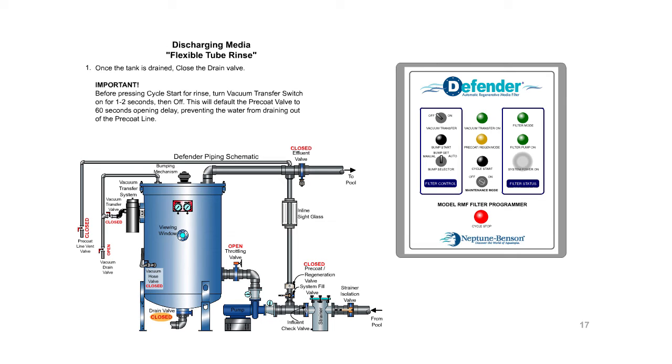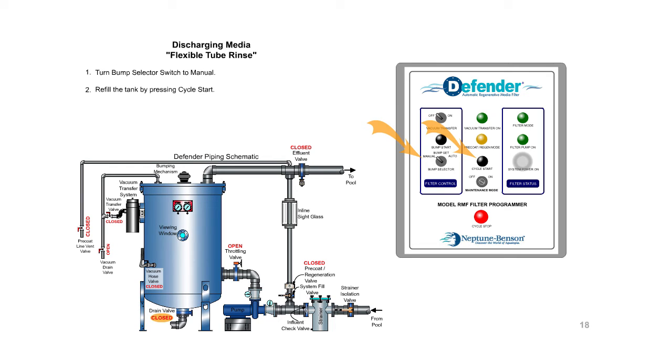Flexible tube rinse. Once the tank is drained, close the drain valve. Before pressing cycle start for rinse, turn vacuum transfer switch on for 1 to 2 seconds, then off. This will default to the pre-coat valve to 60 seconds opening delay, preventing the water from draining out of the pre-coat line. Turn bump selector switch to manual. Refill the tank by pressing cycle start.